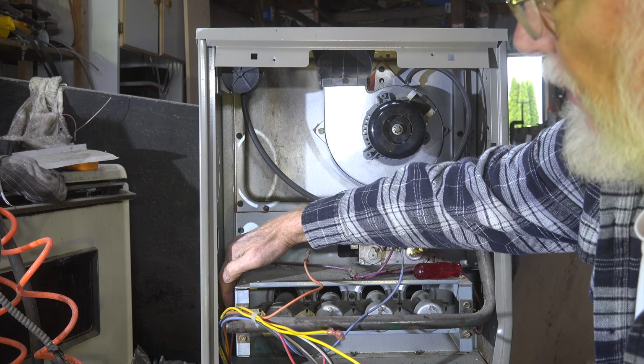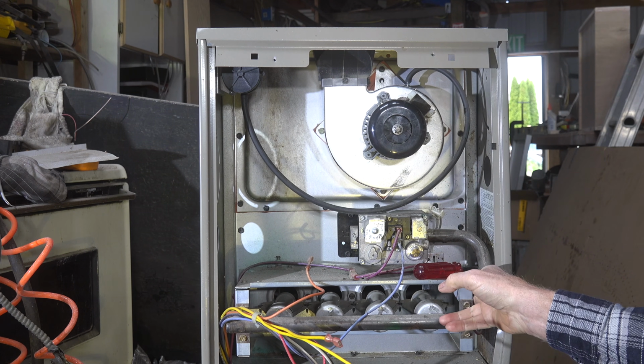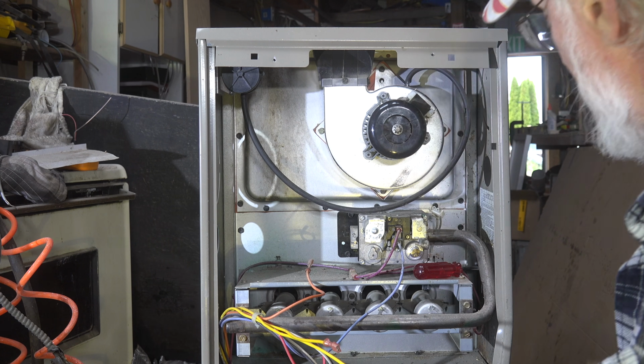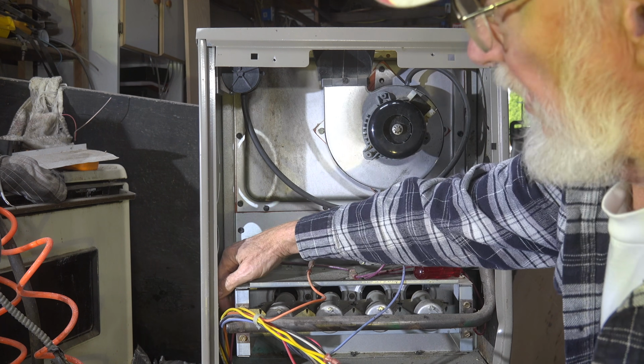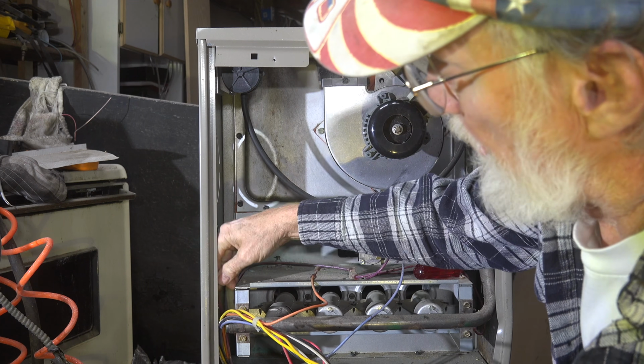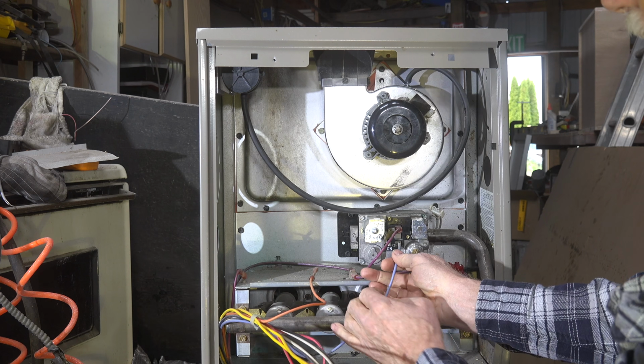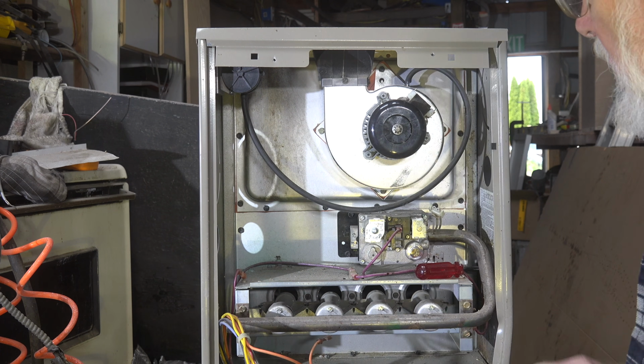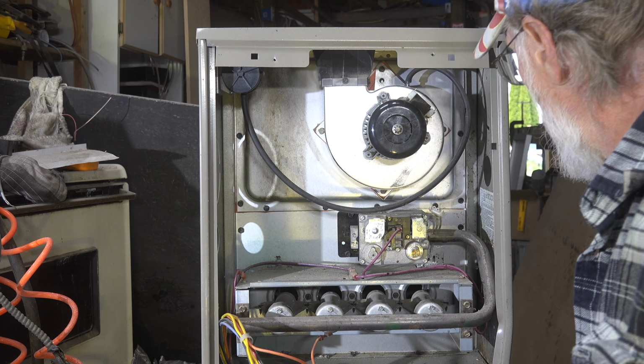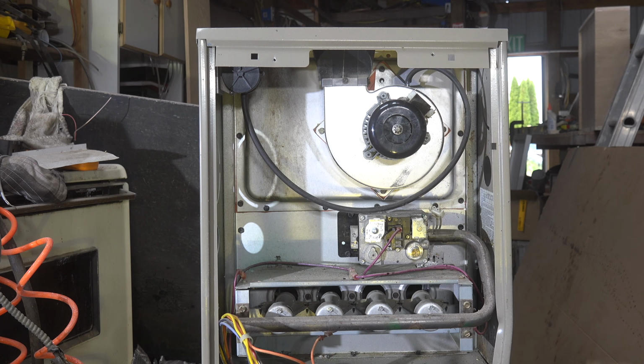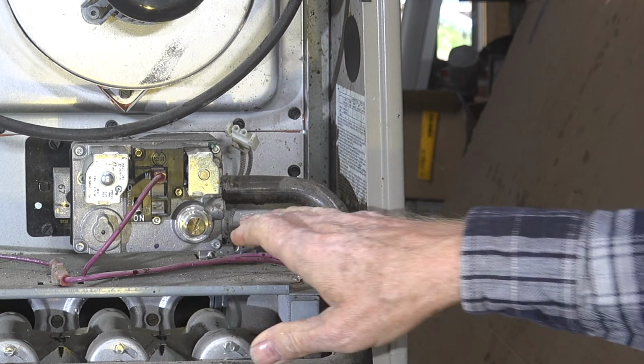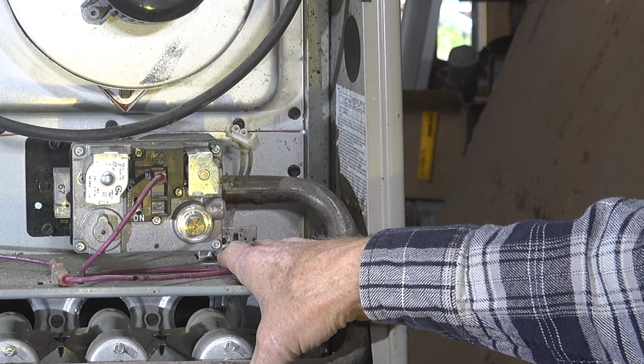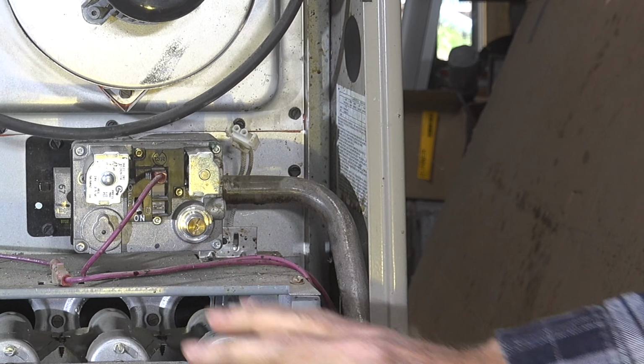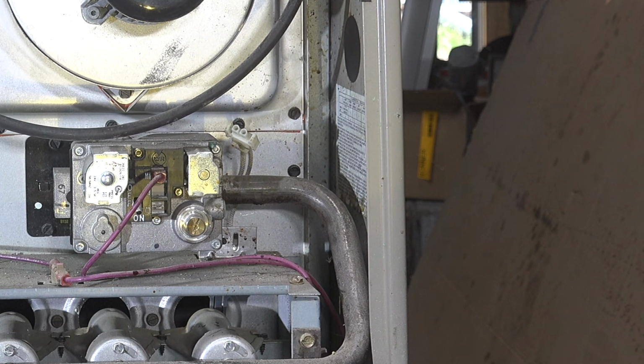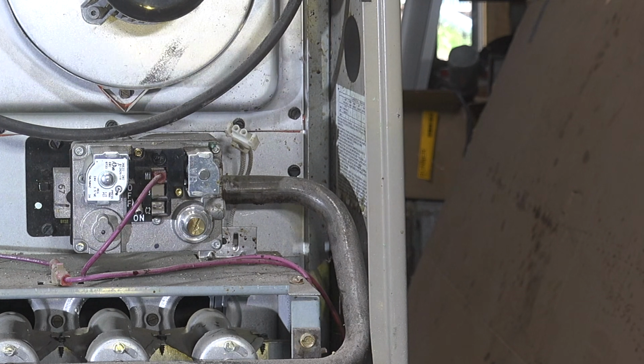Now these rollout switches—rollout switch here, rollout switch here, rollout switch there—I would just leave that wiring in except for the last wire. On this one, there's a wire going down here; I'd pull it off. You only have to take off one wire off of the gas valve. The rest of these wires can all stay on because this whole assembly is going to be removed. The one thing you do need to get out is the hot surface igniter, right here. You can take out this whole assembly without removing the hot surface igniter, but it's pretty easy to damage anyway.